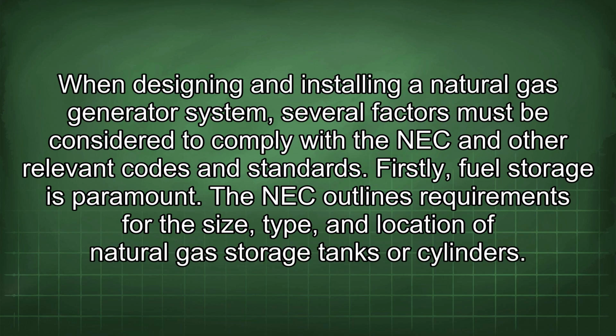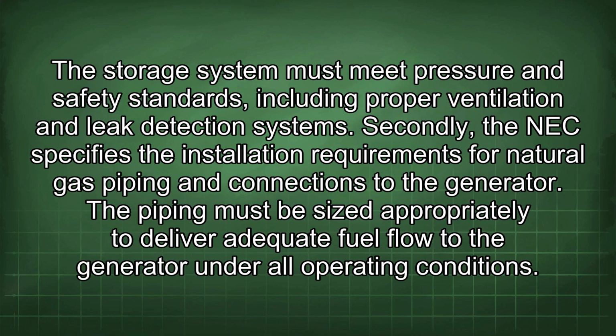When designing and installing a natural gas generator system, several factors must be considered to comply with the NEC and other relevant codes and standards. Firstly, fuel storage is paramount. The NEC outlines requirements for the size, type, and location of natural gas storage tanks or cylinders. The storage system must meet pressure and safety standards, including proper ventilation and leak detection systems.